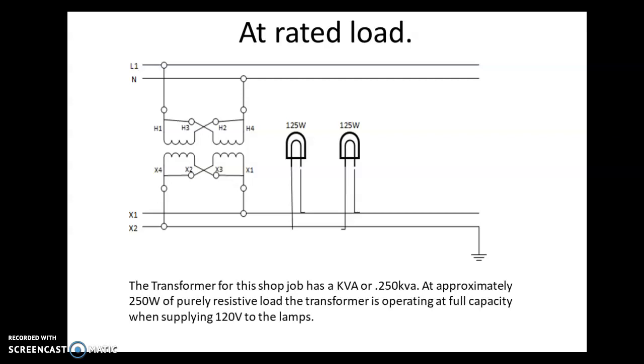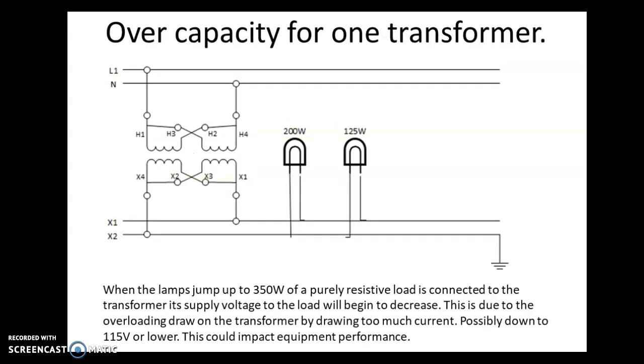Exceeding that kVA rating will cause the voltage to start to drop or dip. So if we went up to 325 or 350, the lamps drawing too much current will cause the voltage to start to diminish or decrease from what we're expecting, which is that 120 volt range. You might see something as far as 115 or lower. This could impact the equipment performance. Sometimes, I don't know if you've ever experienced this, but if you're using an air compressor out of the garage and you're too far away from the main service, sometimes the air compressor will appear to not work or turn off, kicking out on low voltage.